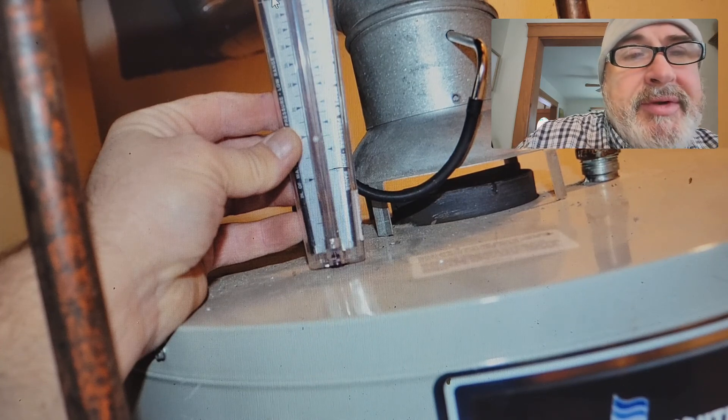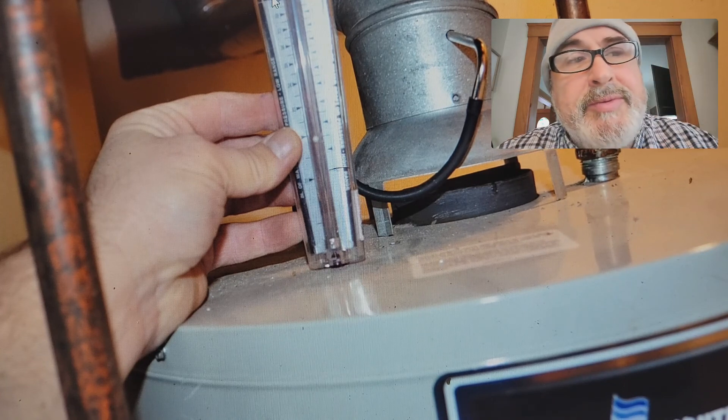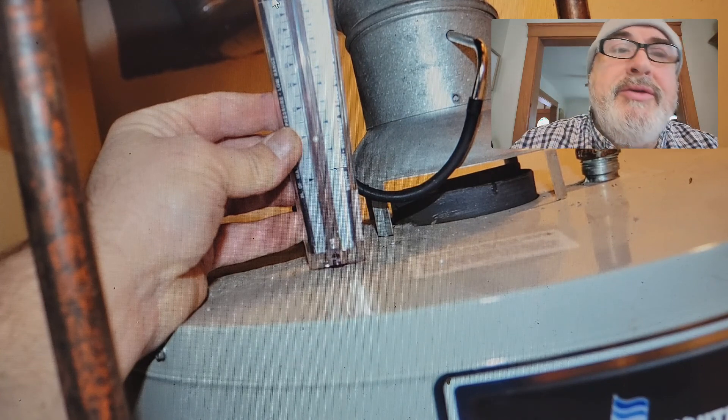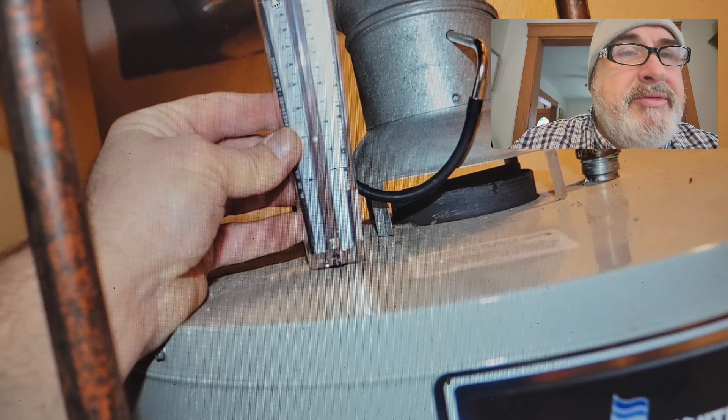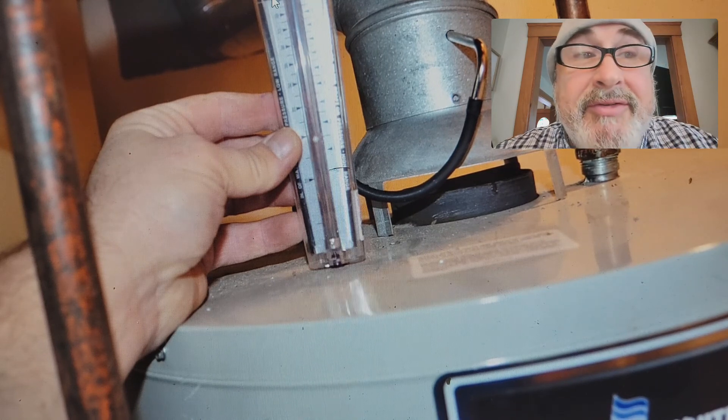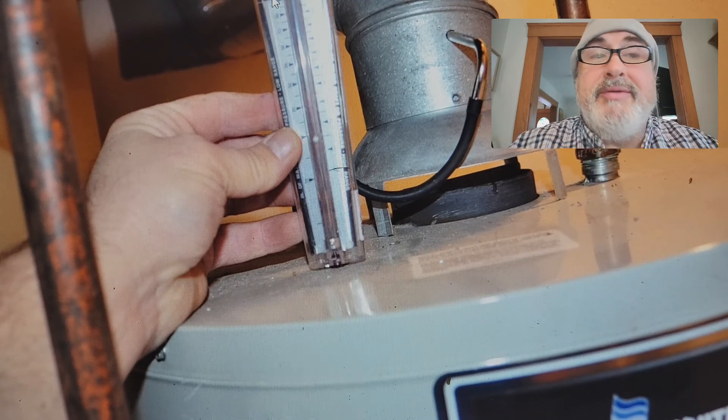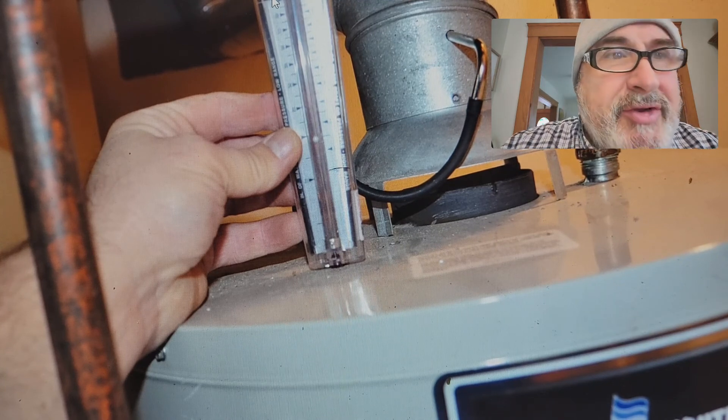New furnaces. A lot of times you have issues where you have an old furnace with a high stack temperature and then a new furnace because you could connect the old furnace to the same pipe as the water heater. But now you have a high efficiency furnace. So now that the stack temperature drops, all of a sudden the draft changes.